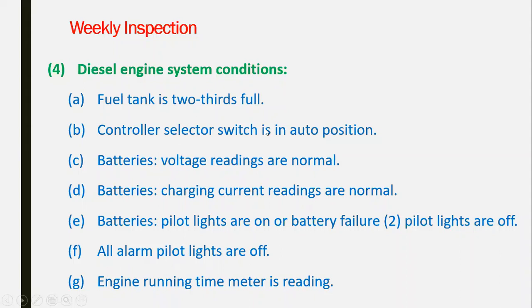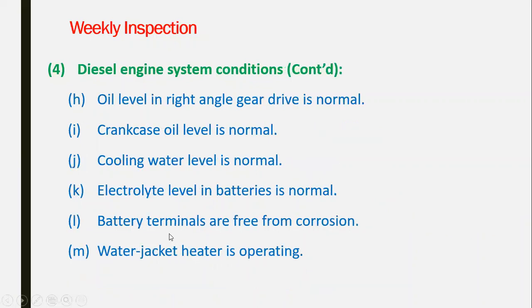Controller selector switch is on the auto position. The batteries: reading the voltage is normal. For the batteries for the diesel engine to start up, the charging current is normal. Pilot for the batteries is on. Alarm pilot light is off. Engine running time meter is reading. The oil level is normal.